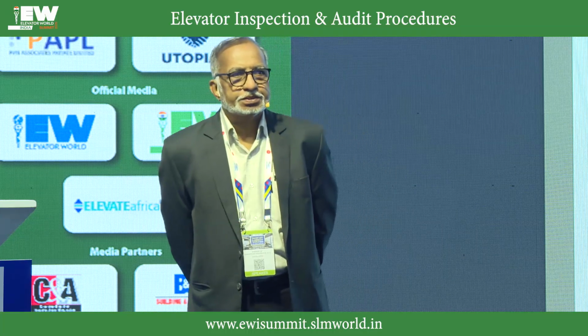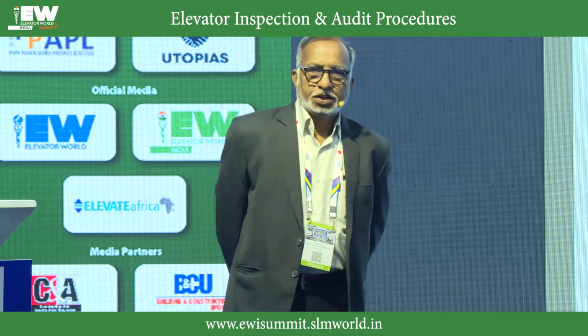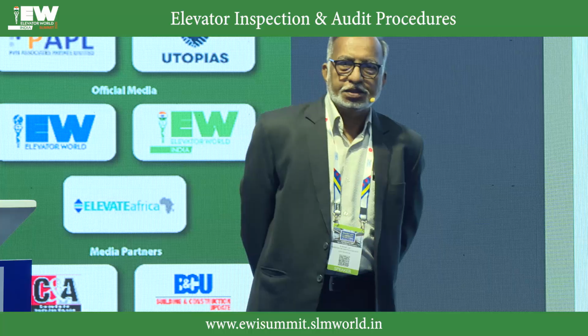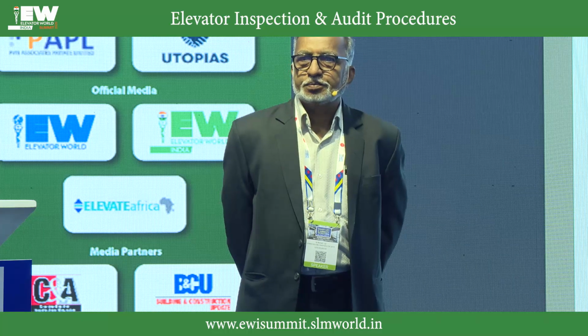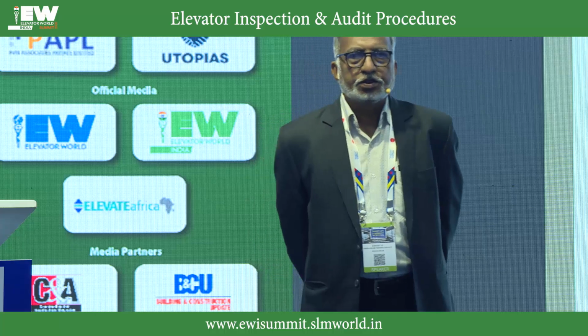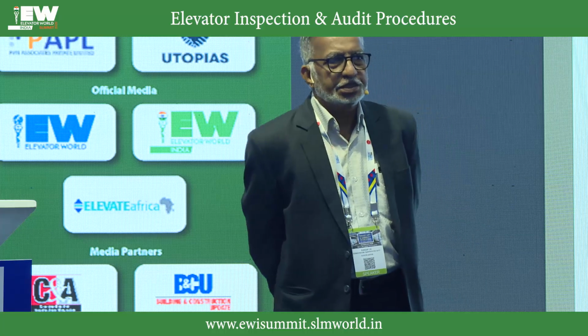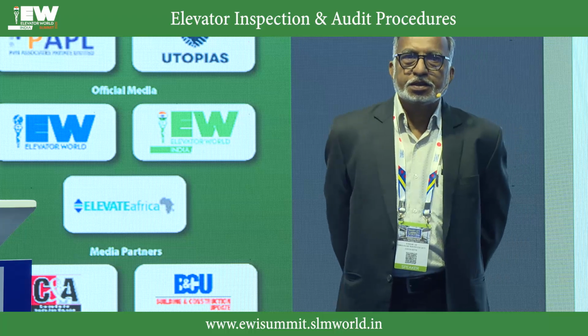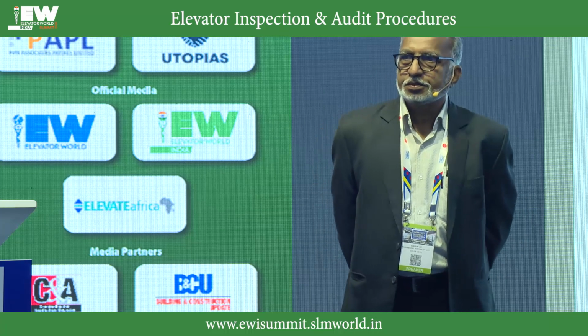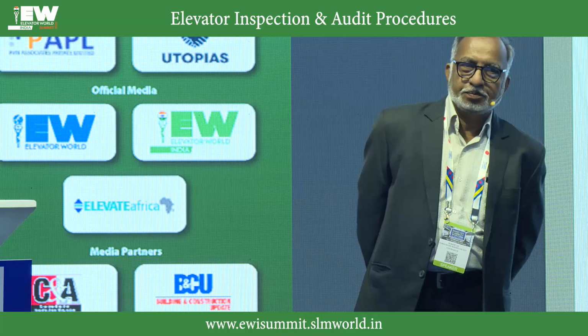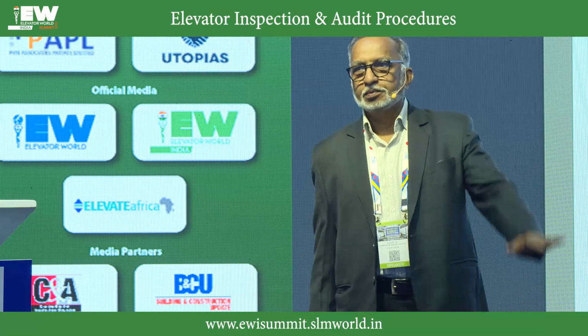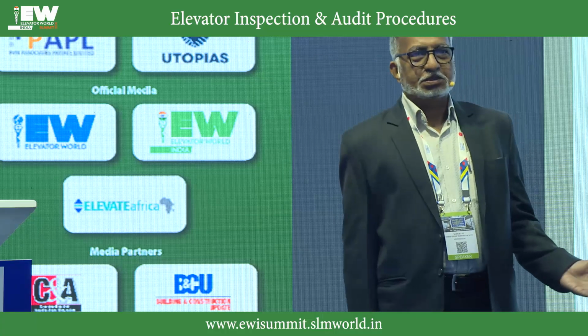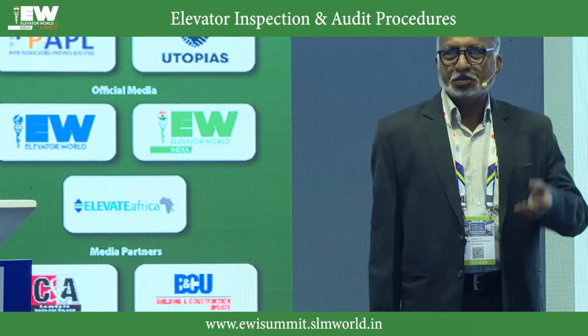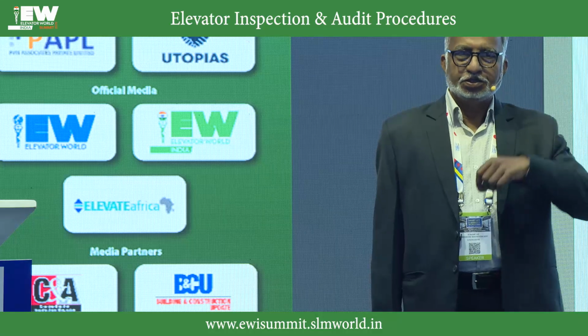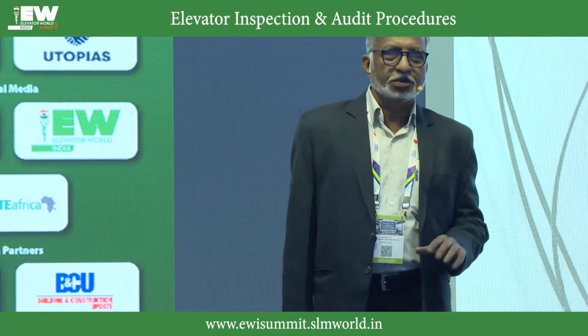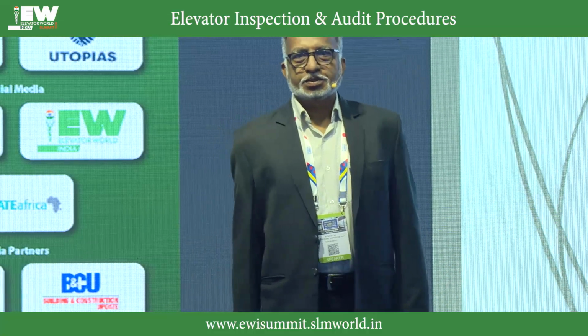Then fireman switch operation. The fireman switch is at the ground floor, and in case of fire, the fire people get control of the elevator by switching on the fireman switch, which is generally installed at the ground floor or the podium where the fire brigade can take their vehicle. I have seen one site where the fire tender was able to come to the podium level and the fireman switch was installed in the basement. So what is the use of that? In case of fire, if you break open the fireman switch, the lift will come down to the basement, not to the podium level, because the fireman control switch is installed at the basement level.